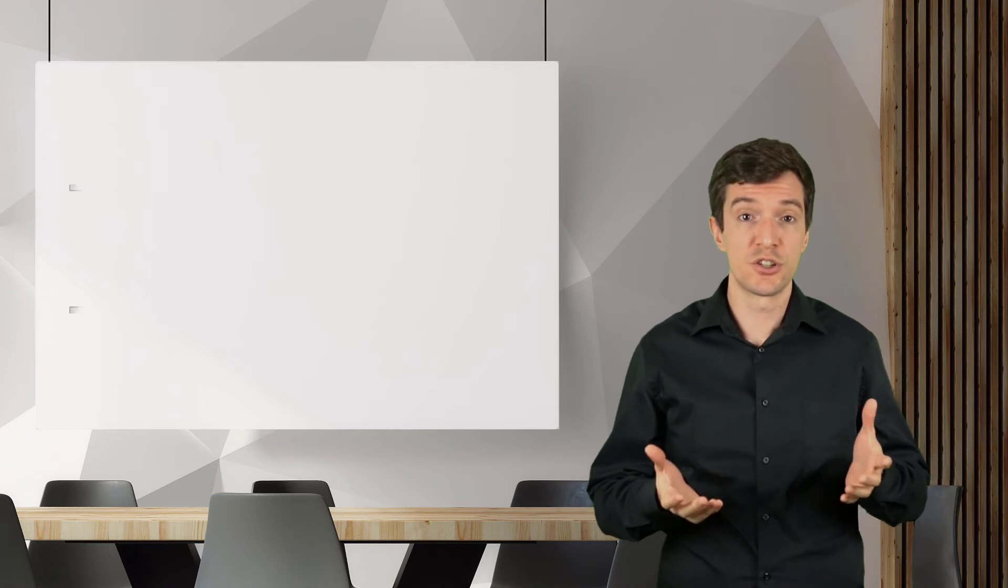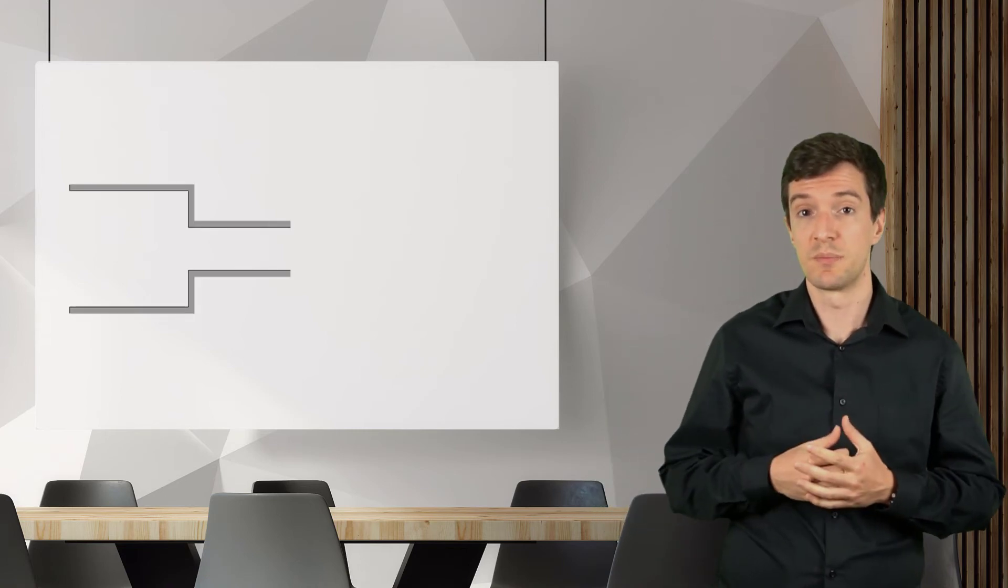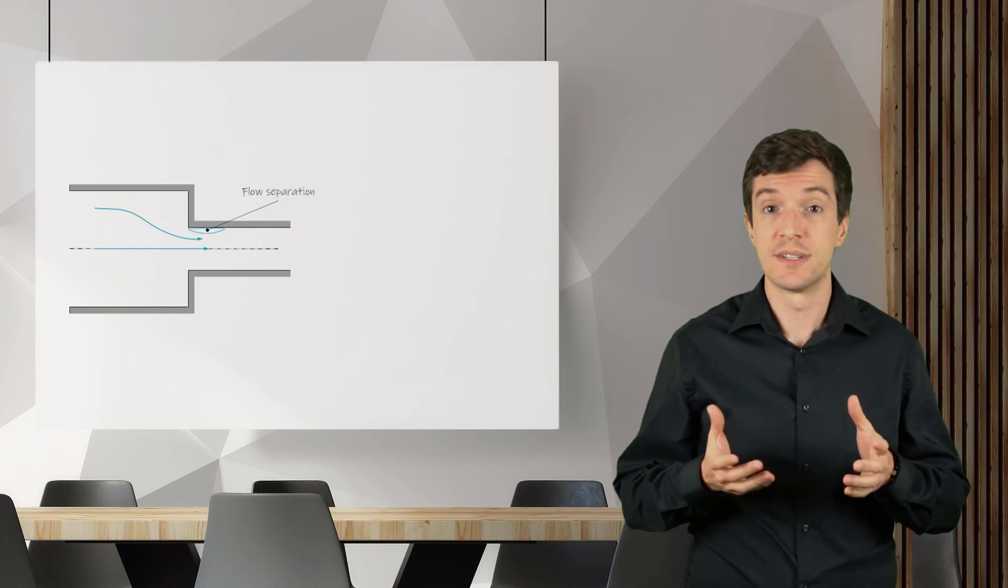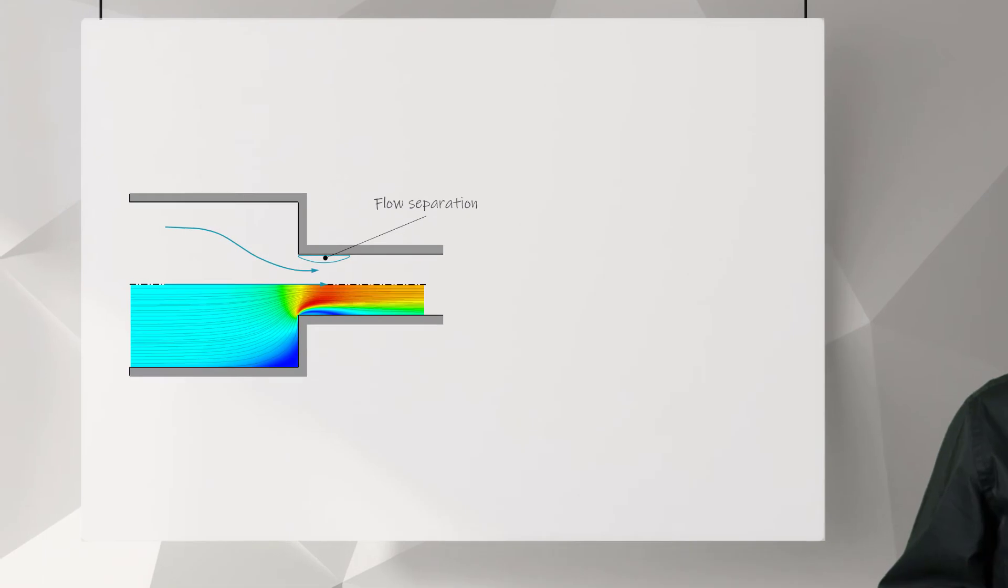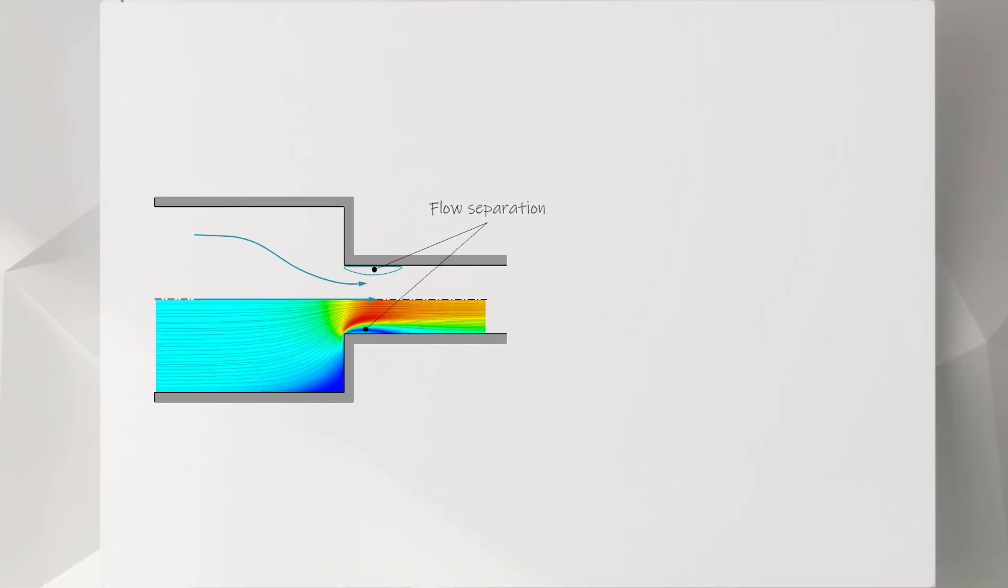Similar to the entrance region is the sudden contraction in pipes and channels. We often encounter this component when larger pipes are connected to smaller pipes. The contraction works in a similar way as the entrance region where we can have separated flow. The flow initially accelerates and then decelerates in the smaller pipe. The loss coefficient is related to the ratio of the cross sectional areas of the two pipes. The closer are the areas, the smaller the loss coefficient will be.